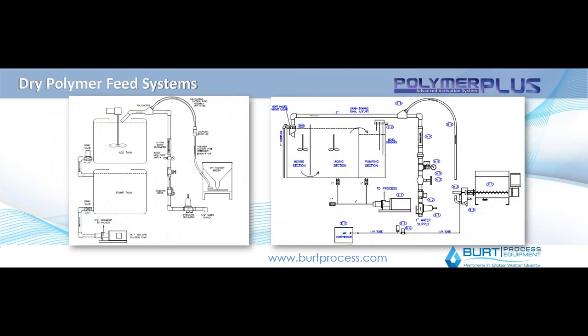These are a couple of different examples showing how this looks quite a bit different from how liquid-based polymer systems operate. On the left, you have a dry polymer feeder drawn up, then a polyductor where city water is transferred through. It blends and gets put into the tank where it's agitated to allow for mixing — using a gentle mixer, not a shear mixer. This is also the aging tank where the polymer is allowed to sit for an amount of time depending on the polymer, anywhere from 20–30 minutes up to a couple of hours, and is then transferred into the pump tank for actual use.